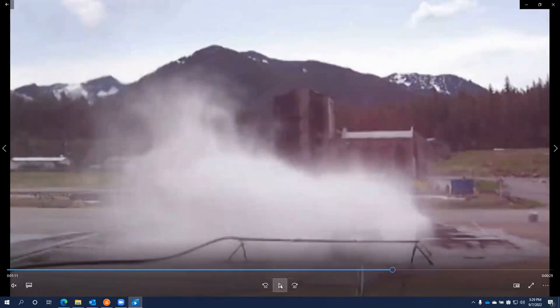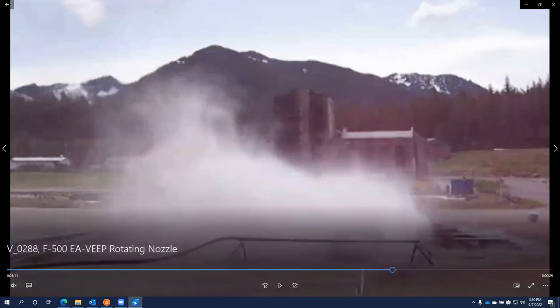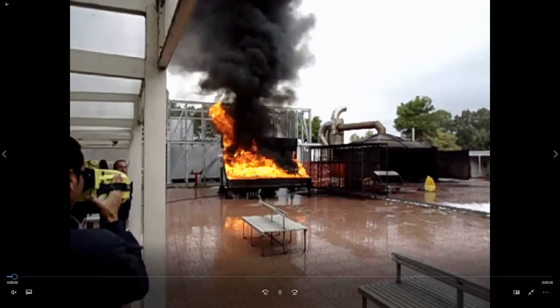We can use this agent in a preventative way. Why wait for the explosion and then go put out the fire? So in NFPA 18A, there is a new section, 12.8 I believe, called VEEP, Vapor Encapsulation Explosion Prevention. It talks about utilizing VEEP, using manual application devices as well as fixed application devices. The reason both are in here is because of something we did with the Italian Navy.